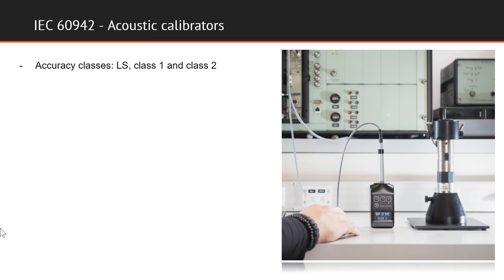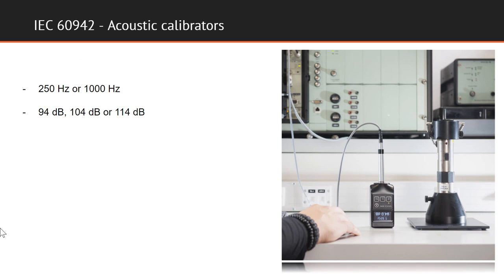This standard defines three classes of accuracy: LS, 1, and 2. Class LS is intended for laboratory use, while Class 1 and 2 are intended for field use. Calibration is performed at a single frequency, either at 250 or 1000 Hz, and at supported acoustic pressure levels, which are usually either 94, 104 or 114 dB.